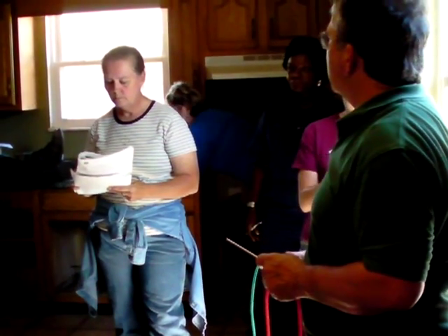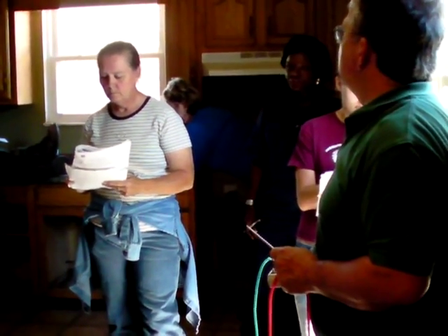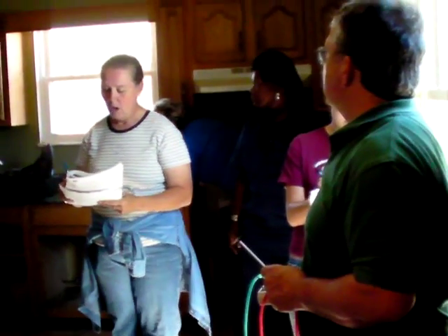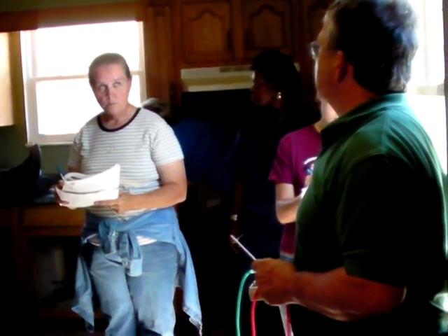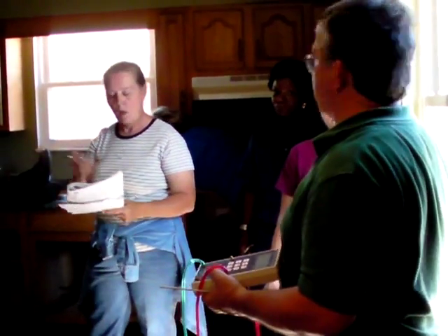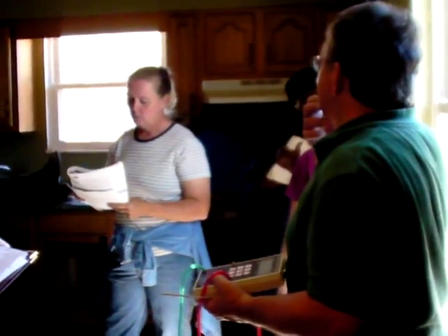So with everything we've done, if this went past a -5, like if it was -6, then you eliminate doing any of it under worst case conditions. That's right, it'll be natural. -5 is the indicator: turn the fans off, lower the pressure in the house, turn all the rest of the equipment off, and you do that piece of equipment only under natural conditions. I could even open up the doors at that point, if I wanted to.